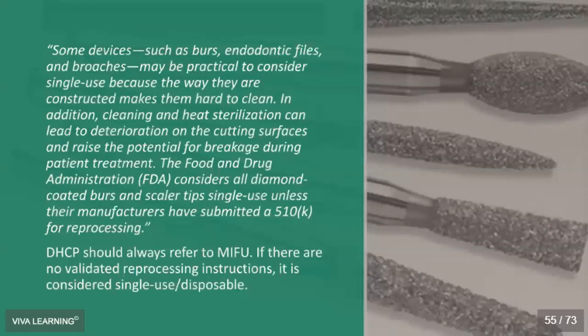And the FDA considers, get this, the FDA, here they are again, considers all diamond-coated burrs and scalers single use unless the manufacturers have submitted a 510(k) for reprocessing. And I will tell you, as of today's presentation, they don't have any on file. So that tells us that we should be treating diamond-coated burrs and scaler tips as single-use currently. So again, I'm going to tell you to always refer to the manufacturer's IFU. If there are no validated reprocessing instructions, it really should be considered a single-use disposable item.